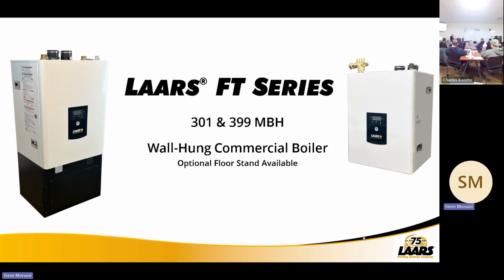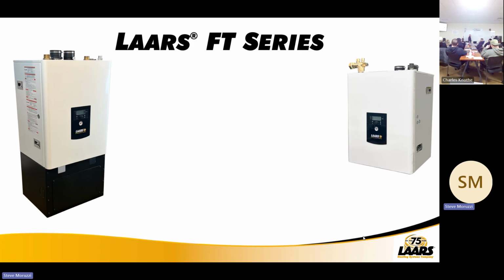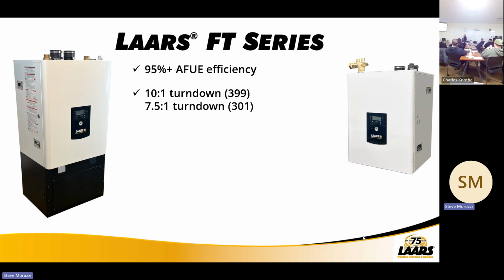And someone was asking me earlier about a floor stand, okay? And you can order it either way, or just purchase the floor stand. So you can hang these right on the wall, or I prefer floor standing. Again, you get into a 301 or 399,000, you add water to that heat exchanger, you got some weight on it. And the floor, we can go top or bottom connect with this, and we'll talk about that in a minute. So 95% AFUE, we have 10-to-1 turn down on the 399,000 BTU model, and a 7.5-to-1 on the 301 model.